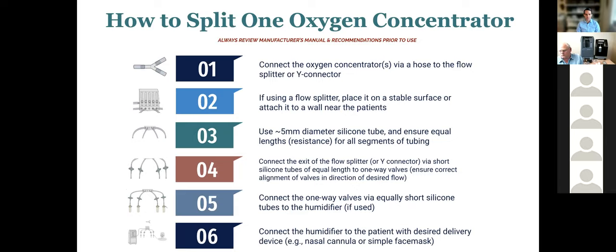If you are using a flow splitter, these can be delicate. And so make sure that these are placed somewhere where they're not going to get knocked over or dropped. There's some variability in what can be used to connect these, but in general, something around a 5 millimeter diameter silicone tubing. Keep an eye on lengths to make sure that resistance is the same. If you use different lengths for each arm of the split, then what the patients may ultimately be receiving is going to be a little different. So just keep an eye on that.